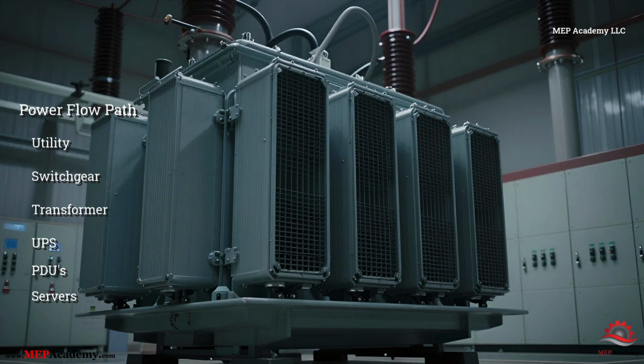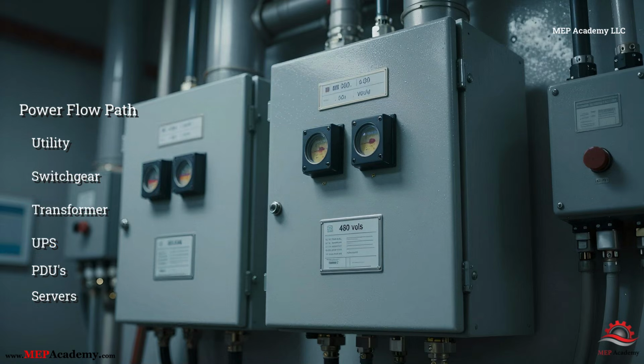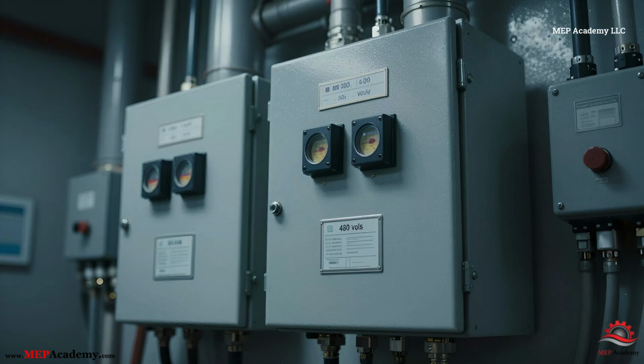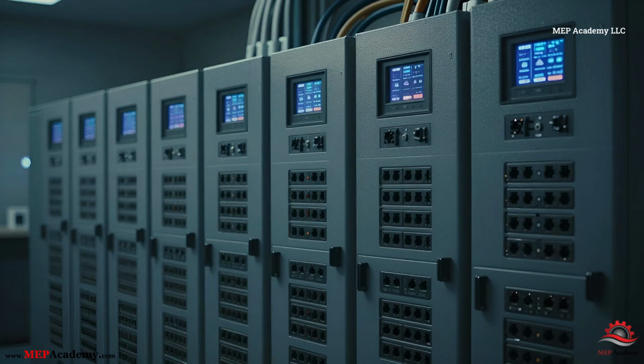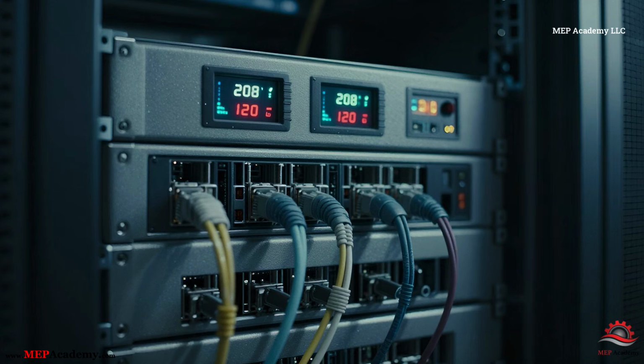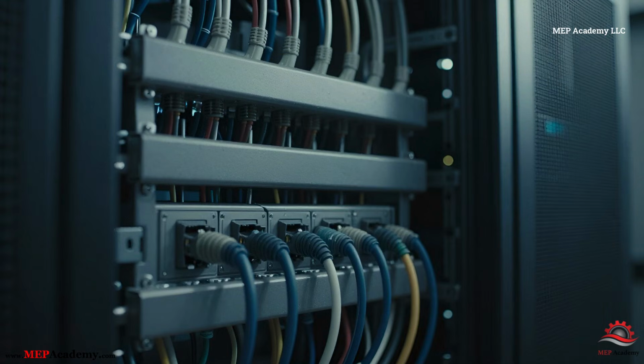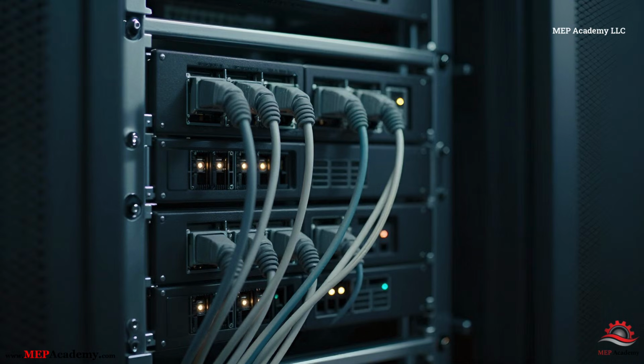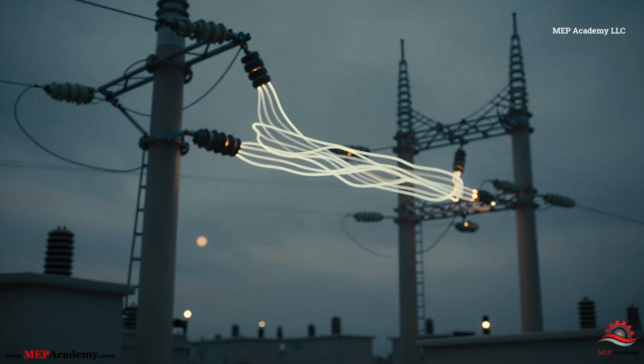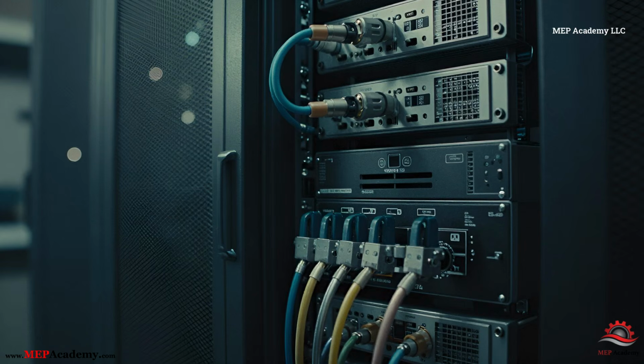From switchgear, the electricity moves into step-down transformers. Transformers reduce the voltage to levels that are more suitable for the building's electrical systems. For example, the voltage may be stepped down to 480 volts, which is commonly used for large equipment and electrical distribution systems inside commercial buildings. From there, power flows into power distribution units, often called PDUs. PDUs take that 480-volt power and convert it again to voltages used by server equipment, such as 208 volts or 120 volts. Finally, the electricity travels through branch circuits and rack power strips that supply power directly to individual servers inside the racks. So the electrical path inside a data center is essentially a series of controlled voltage transformations and distribution steps, moving power from high-voltage utility supply all the way down to the sensitive electronics running inside the servers.